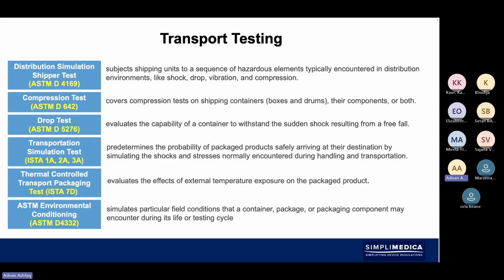There are specific standards required, ASTM standards D4169, and then the subset, and then ISTA levels of testing, where you would then expose the device and the packaging to compression testing or drop testing or vibration testing, and then also environmental conditioning, that the device's packaging withstands all the pressures once it's been through all of those simulated tests.